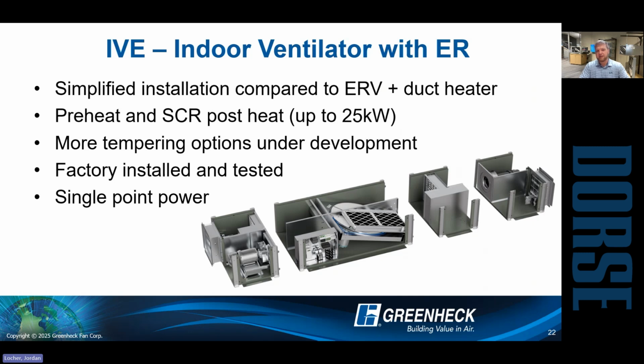And really the advantage here, we see a lot of times using an ERV, we might want to boost that supply temperature just a little bit higher. Might be a little bit cold and frigid coming off of that wheel. So adding an SCR controlled electric heater, some of the advantages of that: one, you can hit whatever LAT you're looking for. And two, this is all factory installed, factory tested and single point wired. So if you compare that to just an ERV with a field installed duct heater, it's a very clean, very well designed package that reduces some of that hassle of installing it in the field.